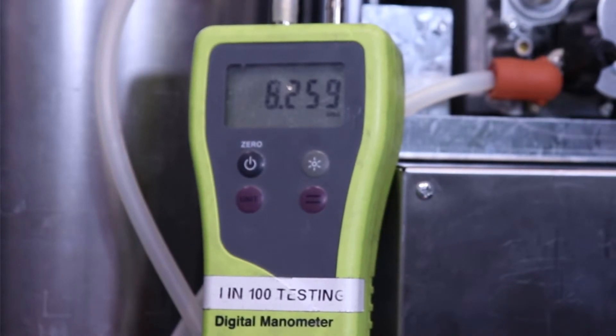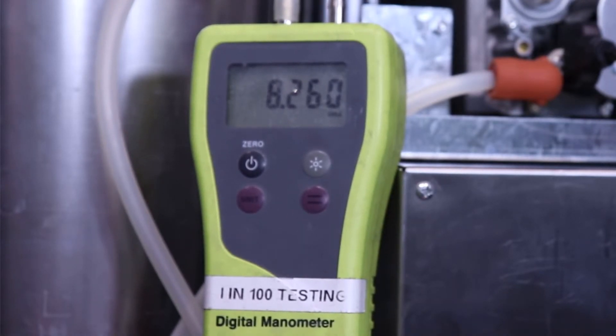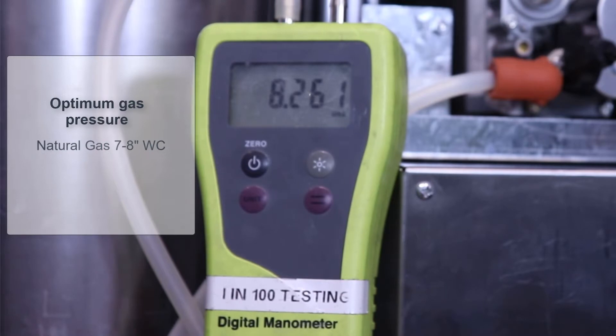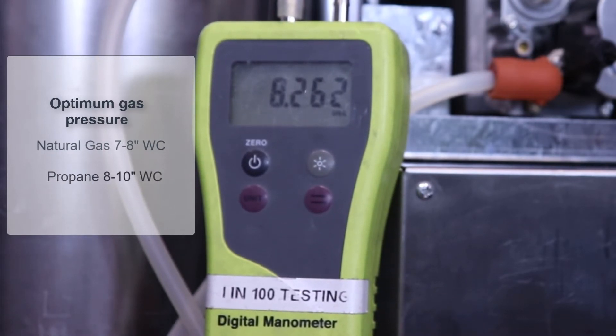The optimum gas supply pressure for the SL series boilers is 7 to 8 inches for natural gas boilers, 8 to 10 inches water column for propane boilers.